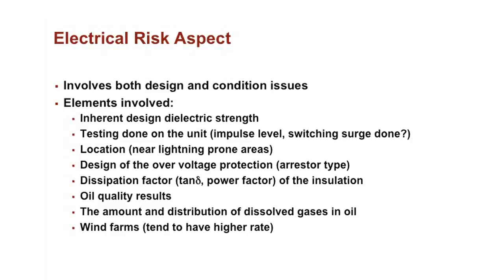And then there's the design of the overvoltage protection equipment. A lot of transformers will have some kind of arrestors on them. And if they're modern type arrestors like zinc oxide, then the transformer is virtually protected from seeing a lightning impulse. So knowing what type of arrestors are on the transformers is very important for calculating a risk factor.